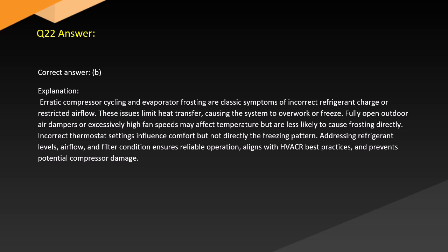Answer. Correct answer: B. Explanation. Erratic compressor cycling and evaporator frosting are classic symptoms of incorrect refrigerant charge or restricted airflow. These issues limit heat transfer, causing the system to overwork or freeze. Fully open outdoor air dampers or excessively high fan speeds may affect temperature but are less likely to cause frosting directly. Incorrect thermostat settings influence comfort but not directly the freezing pattern. Checking refrigerant levels, airflow, and filter condition ensures reliable operation, aligns with HVACR best practices, and prevents potential compressor damage.